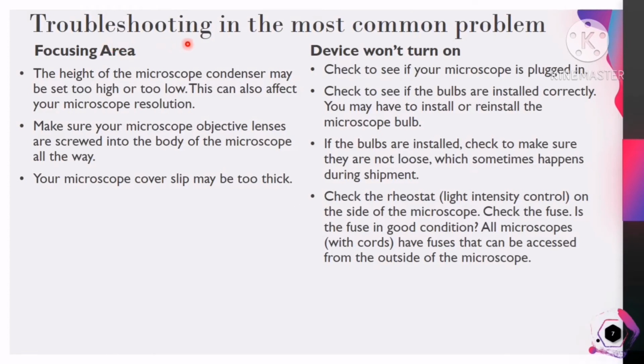This is troubleshooting for the most common problems. There are two: focusing area and device won't turn on. The first one is focusing area. The height of the microscope condenser might be set too high or too low. This can also affect your microscope resolution. Make sure your microscope objective lenses are screwed into the body of the microscope all the way, and your microscope cover slip may be too thick. So you might check on these three first, and then you can troubleshoot it.